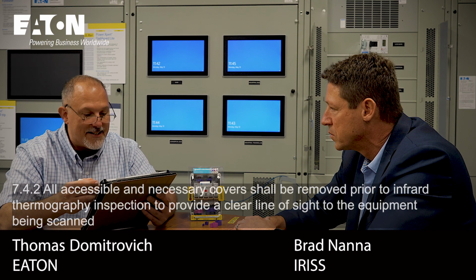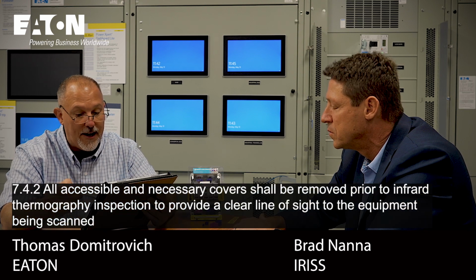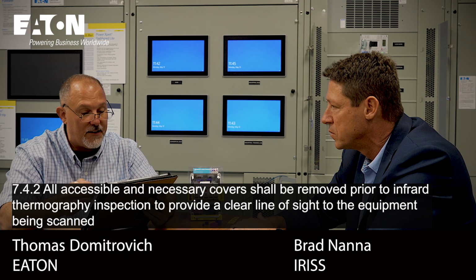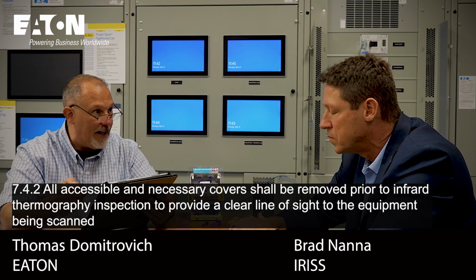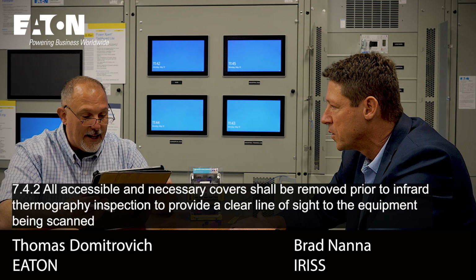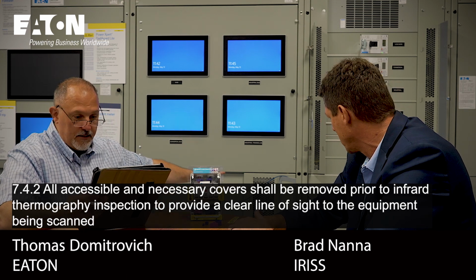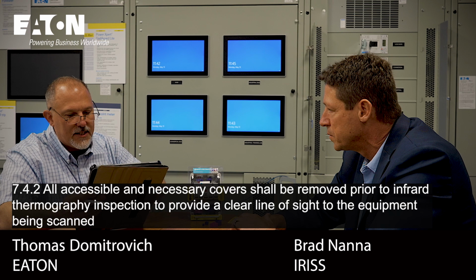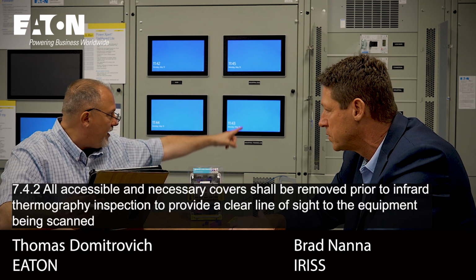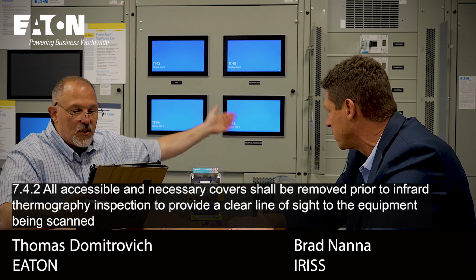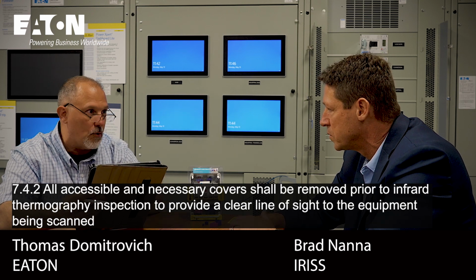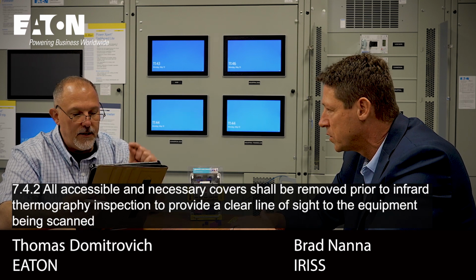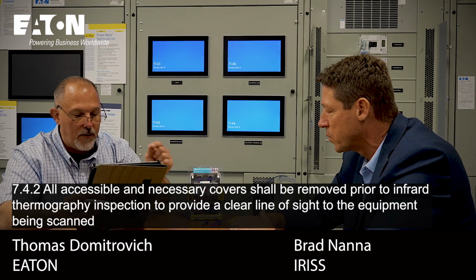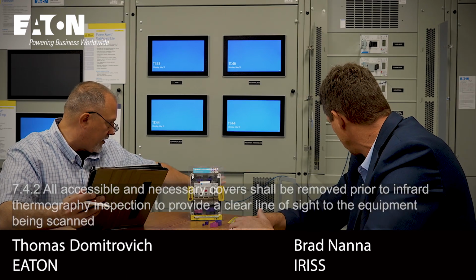So I got language in 7.4 that specifically says all accessible and necessary covers shall be removed prior to infrared thermography inspection to provide a clear line of sight to the equipment being scanned. I think that language would permit this, but we really have to look at it. It says all accessible and necessary covers—so that's a cover, a door, I'd call it. If I changed that, I'd say necessary covers or doors to provide a clear line of sight to the equipment being scanned, which is what that gives you.